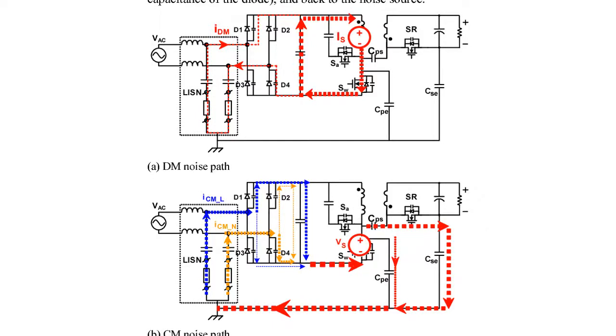From the standpoint of microelectronic circuits, common mode noise is even more potentially harmful than normal mode noise. The biggest source of common mode noise is the difference in potential between two physically remote grounds. The second most significant common mode noise source is the potential due to ungrounded sources.